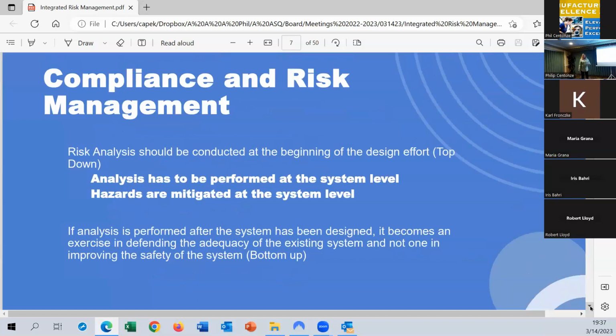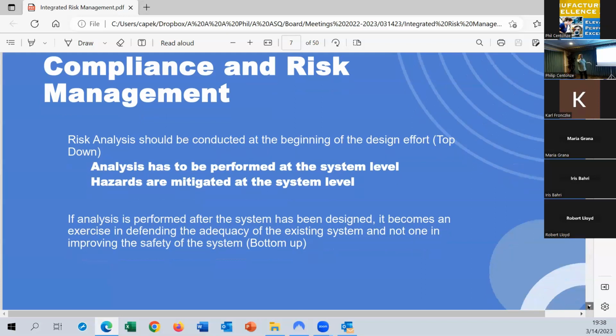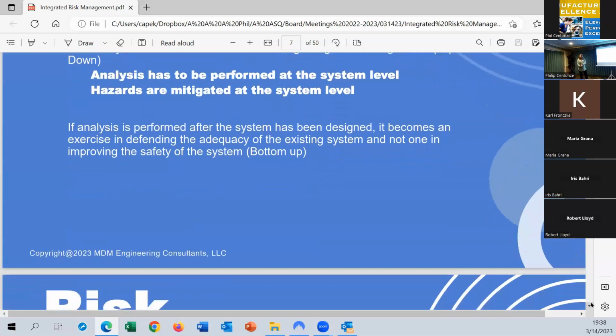So one thing with risk management, and I know we just saw Bob's presentation with mean time to failure, a lot of people sometimes want to do FMEAs. I don't know how many of you are familiar with FMEAs. I'll show you what one looks like in a little bit. But really, you have to do risk management at the system level, because only the system can cause harm, right? So if you have an infusion pump, you're going to have the actual pump, the tubing set that carries, and then the solution bag. You have to look at the totality of the system in order to mitigate risk at the system level. Now, you can look at the infusion pump itself and try to improve its reliability so it doesn't fail, but mitigating risk has to be done at the system level. And that's what we call top-down analysis, as opposed to FMEA, which is more bottom-up.